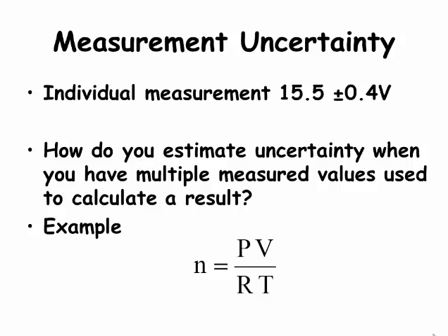Measurement uncertainty tells you and your report readers the uncertainty associated with a measurement in terms of a plus-minus value. Recognizing that every measurement has some uncertainty, an important question is what is the combined impact of all those measurement uncertainties on a calculated result? How do you determine the uncertainty of a calculated value that uses multiple measured values when each measurement has some uncertainty? The purpose of uncertainty analysis is to calculate an uncertainty of a calculated result that involves multiple measured values in the equation, and each measured value has a measurement uncertainty.